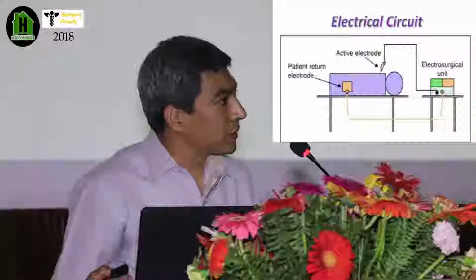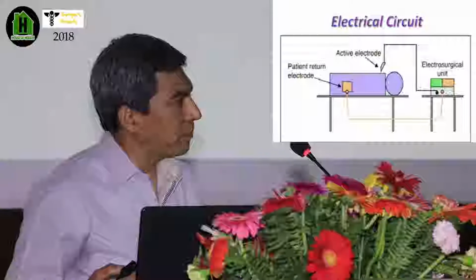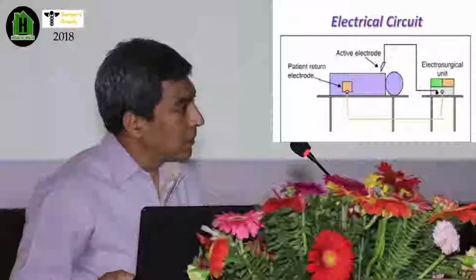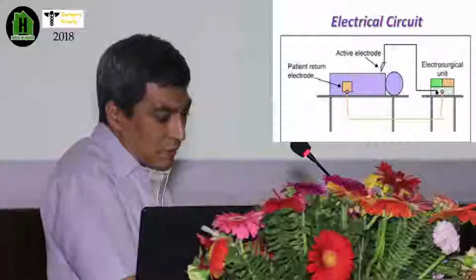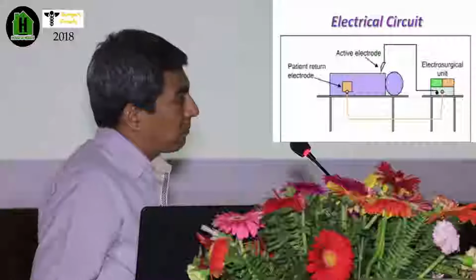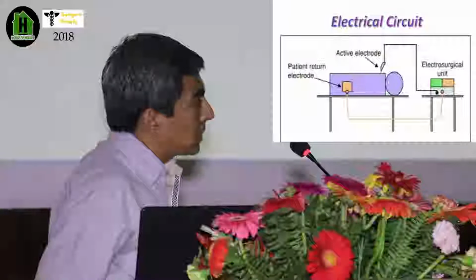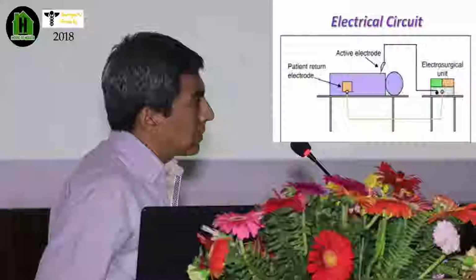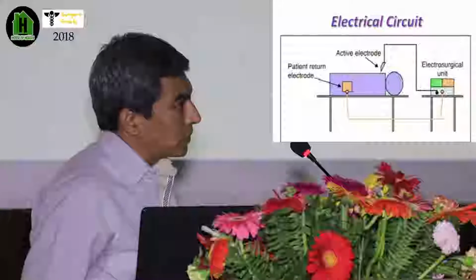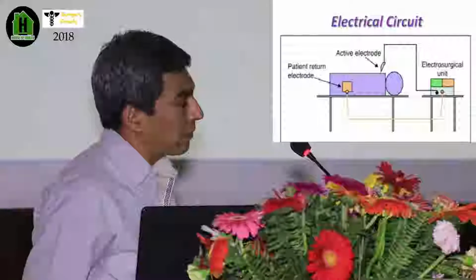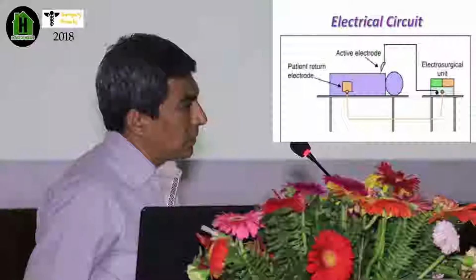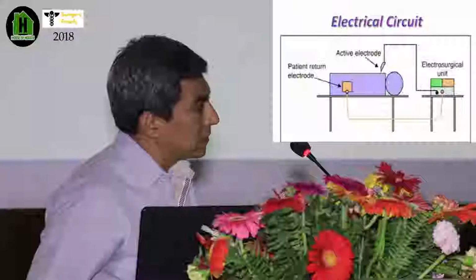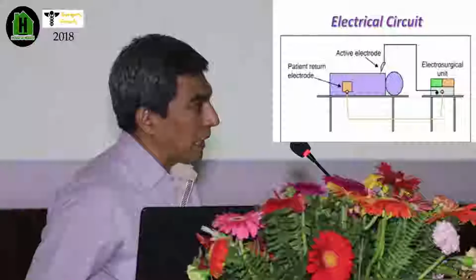So this is the electrosurgical generator. This is a very simple one. It has only very few functions, as you have seen or must have used in your daily practice. But it is not as simple as it looks, because the alternating current received by this generator, something like 50 or 60 hertz, is stepped up about 1,000 times higher than the input. So the output current it produces will be something like 500,000 hertz, or 500 kilohertz, which is tremendously high compared to the input. That is why this kind of instrument can produce an adequate amount of heat in a short duration of time, and it can also produce lots of complications if you do not use it properly and are not aware of the complications, so you might be landed with severe consequences.